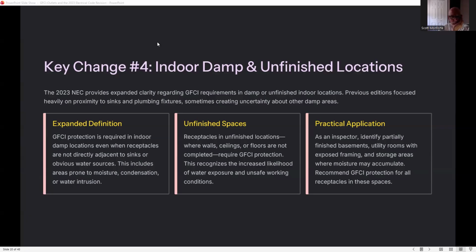Unfinished spaces: receptacles in unfinished locations where walls, ceilings, and floors are not completed require GFCI protection. This recognizes the increased likelihood of water exposure and unsafe working conditions. Practical application: as an inspector identifying partially finished basements, utility rooms with exposed framing, and storage areas where moisture may accumulate, recommend GFCI protection for all the receptacles in these spaces.